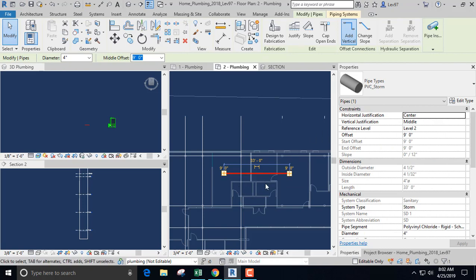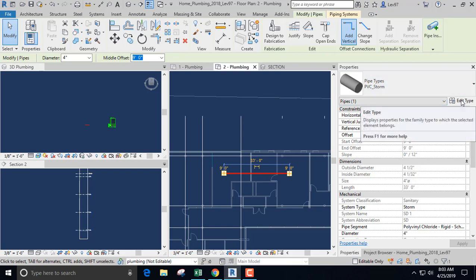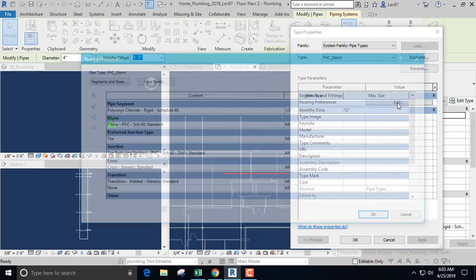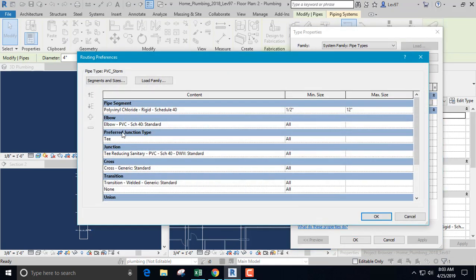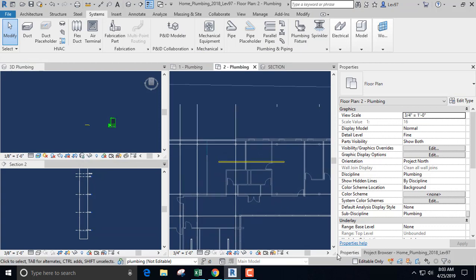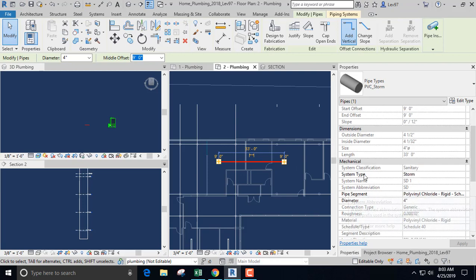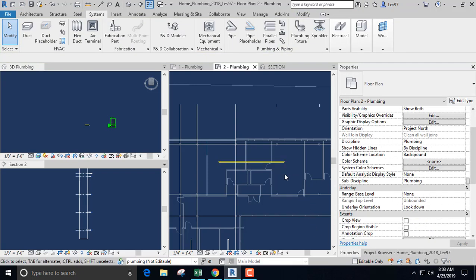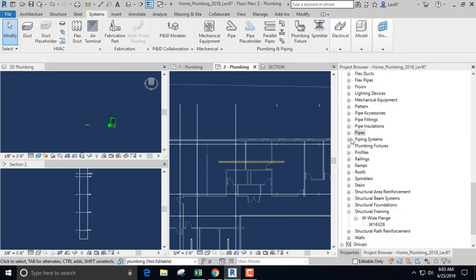For storm drain you'd usually use cast iron — but I shouldn't say 'all the time,' because an engineer will come along and say otherwise, and all the time is not all the time. Now checking the system again — the sanitary is different, that's why I duplicated it. The Revit template really just gives you sanitary to start, so I just made a copy. I just wanted to point that out in case somebody asks.